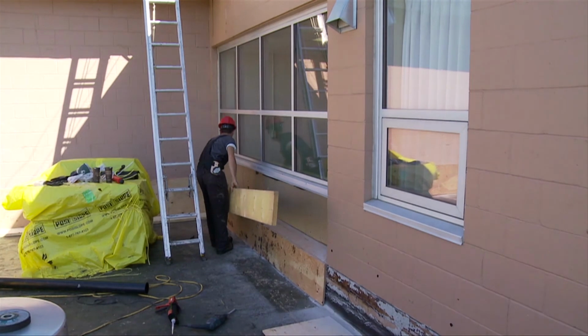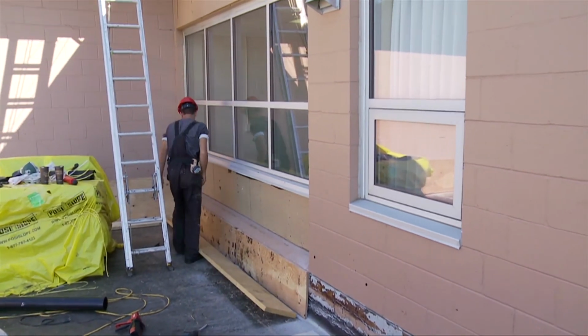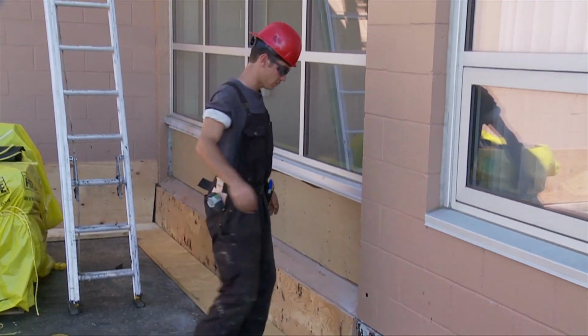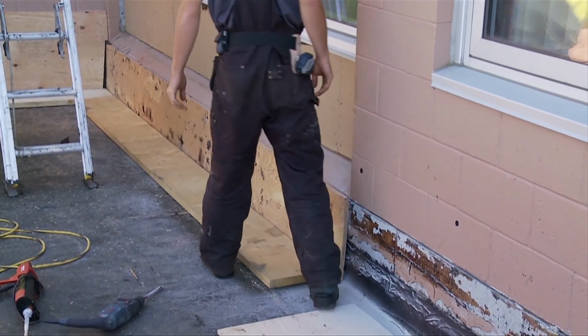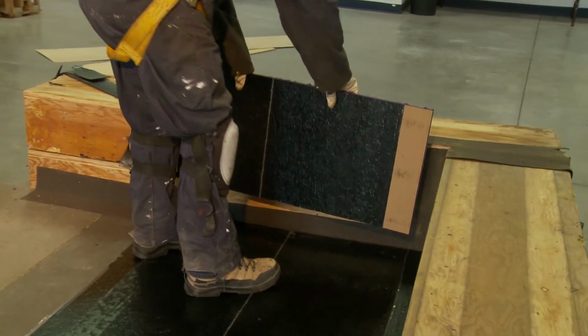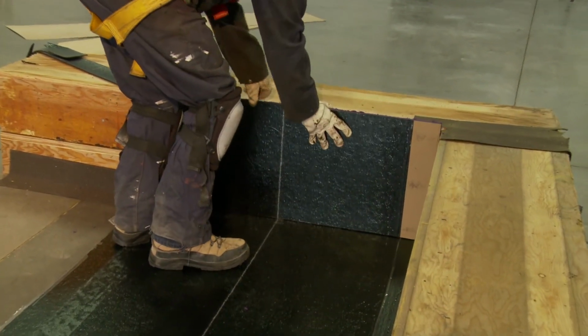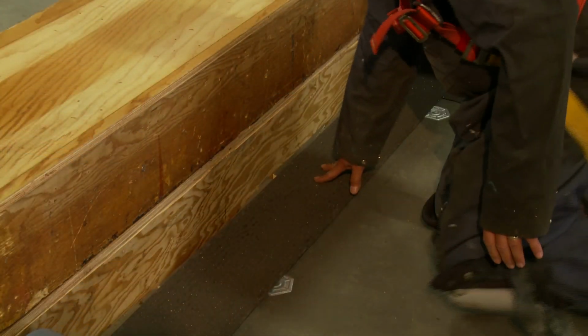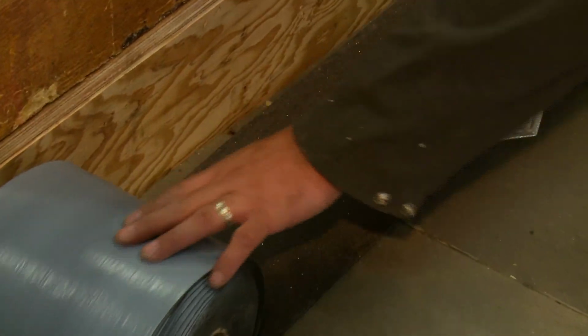Gaps between window openings and frames may be filled with combustible materials. If left unprotected, the torch flame may be drawn into the building between the frame and the wall opening. Protect the fill insulation placed around the frame from flame. Seal gaps and openings with fire prevention tape or self-adhering membrane or metal flashing.